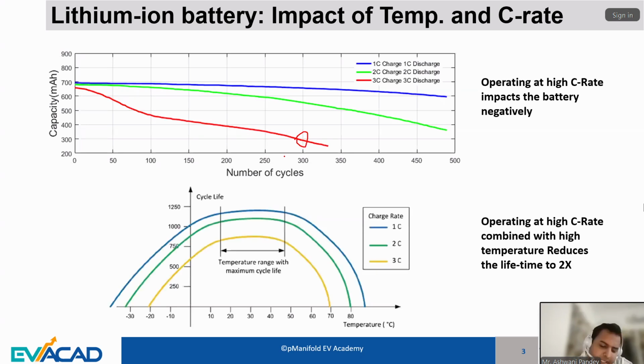Now this rate capability, when combined with higher or lower temperature phenomena, causes the cycle life fading to further increase by twofold. There is an optimum temperature range across which the lithium ion battery performs well - for example, between 15 degrees Celsius and around 45 degrees Celsius, at 1C you can easily achieve around 1200 cycles of operation. At 3C you can achieve maybe 760 to 780 cycles. But the moment you move from the safe operational range to 60 degrees Celsius, you see the cycle fading gap slowly increase.